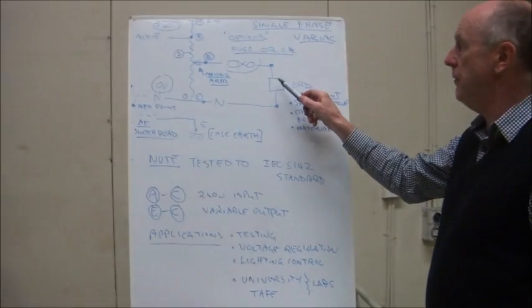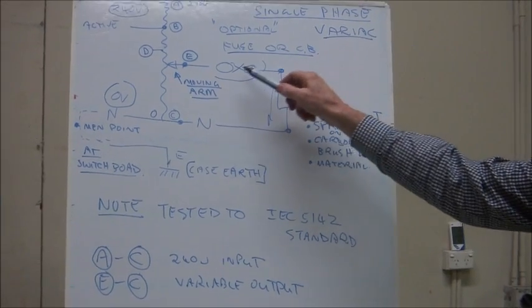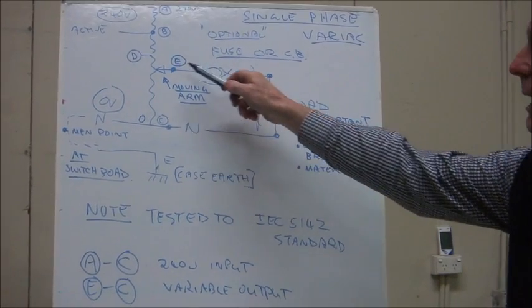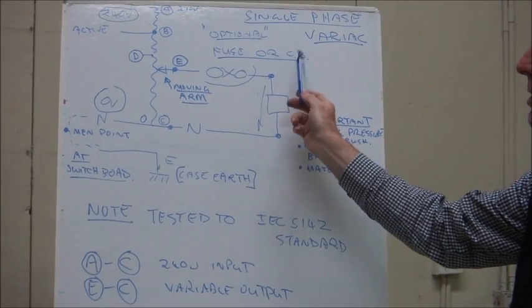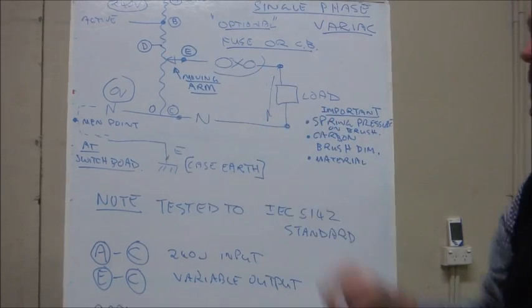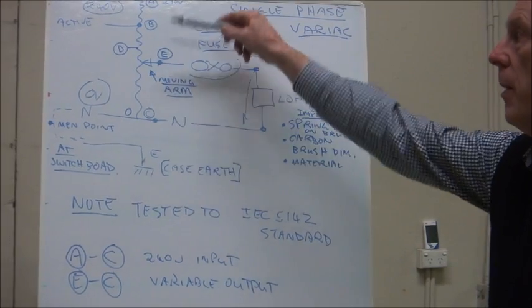This particular variac has fuse protection on the output side, which we show here. Which is very useful because if you have a short on the load side, the fuse will instantaneously blow and protect the windings. If you don't have this or a circuit breaker, you could potentially cause a lot of damage to the variac and mean that it will be unusable. So we strongly recommend fuse or circuit breaker protection on the moving arm.